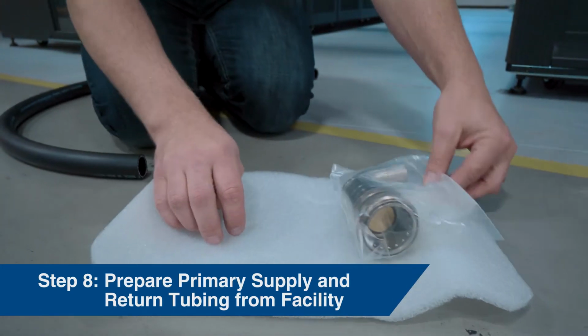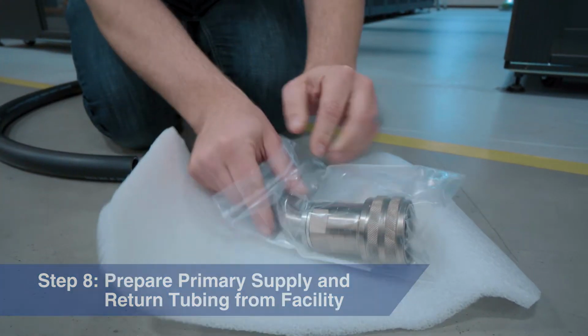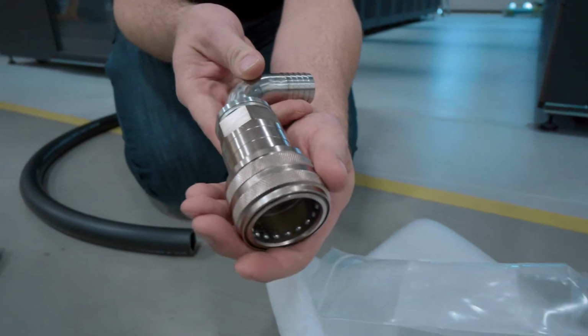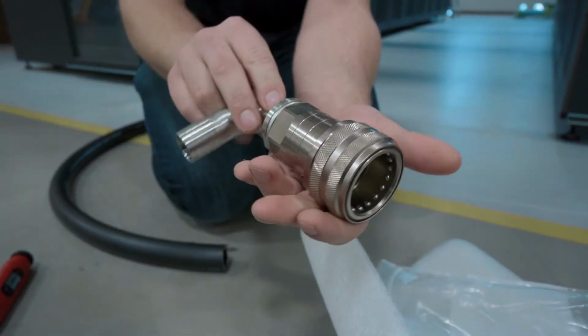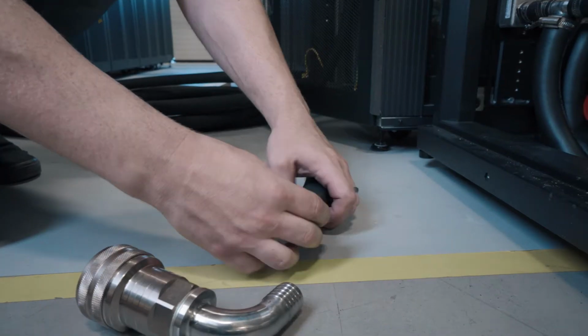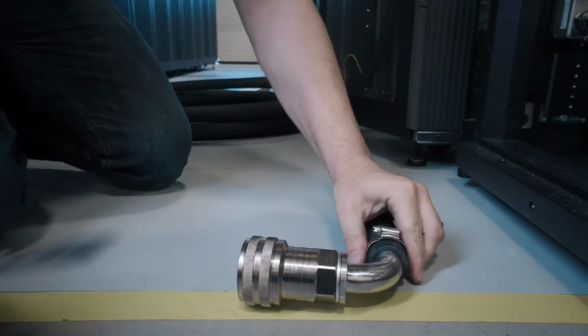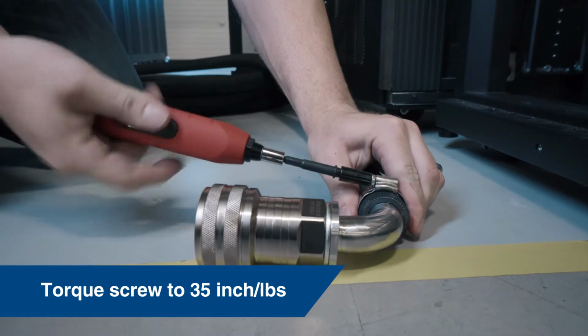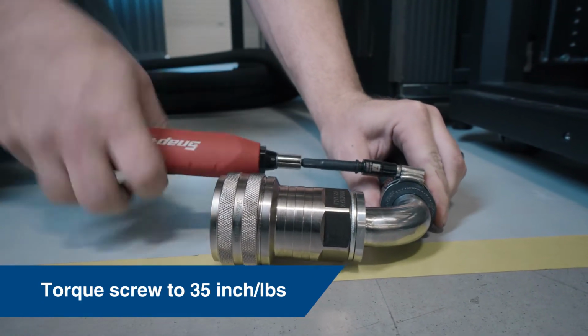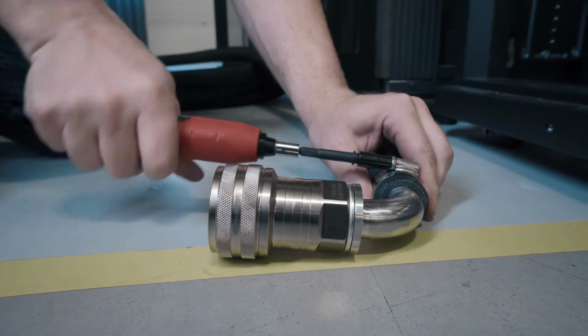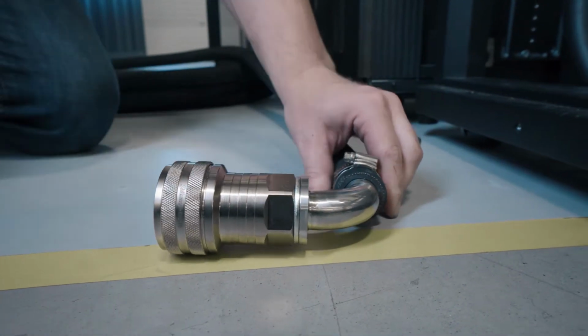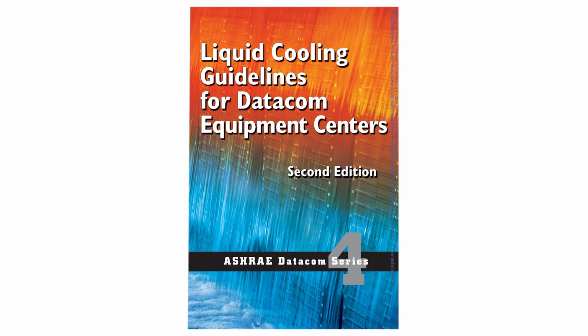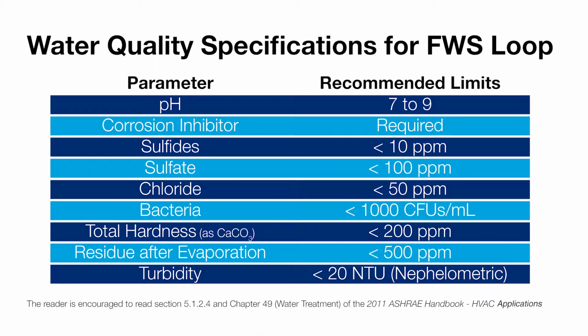Step 8. Prepare primary supply and return tubing from facility. The heat exchanger is supplied with additional quick disconnects that you must connect to your facility tubing so the facility tubes can connect to the primary side of the heat exchanger. Attach the quick disconnects to the hosing and ensure that the tubing can reach the heat exchanger. As a reminder, the facility side liquid must be filtered to 50 microns before entering the heat exchanger to prevent fouling of quick disconnects and other components. It is also recommended that facility liquid meets the ASHRAE liquid cooling guidelines for Datacom Equipment Centers Section 5.1.2.4.